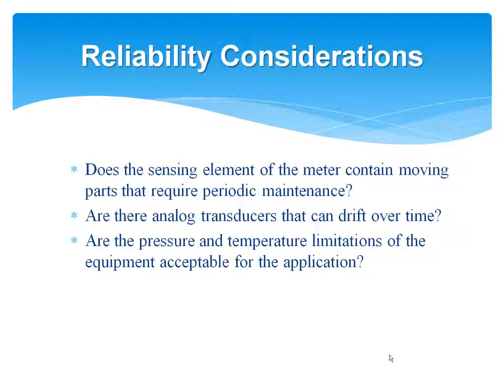The first one is reliability considerations. You have to have a meter out there that's going to work for a good long period of time. So things to take a look at: are there moving parts in the meter technology? If so, in a steam environment, that will likely require some periodic maintenance. If you're doing waste heat recovery on the water side, for example, you've got to make sure that the water is of sufficient quality to be able to have a turbine meter work well over a long period of time. Are there analog transducers that will drift? Can the meter meet the temperature and pressure requirements of a particular application? Are the materials of construction selected properly to prevent corrosion? All those things are going to really factor into the overall reliability of the measurement.